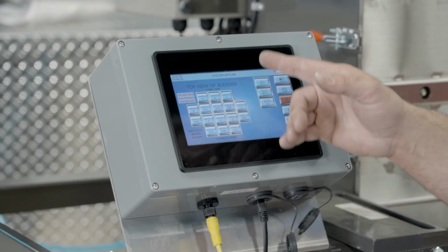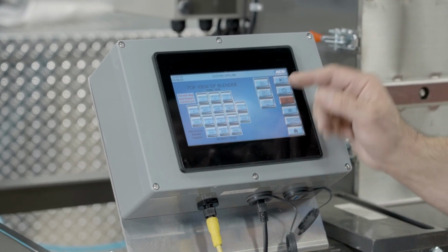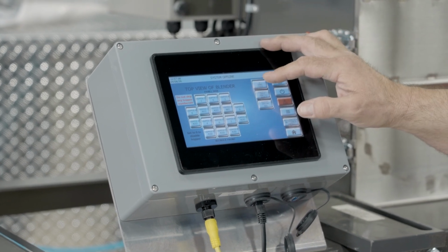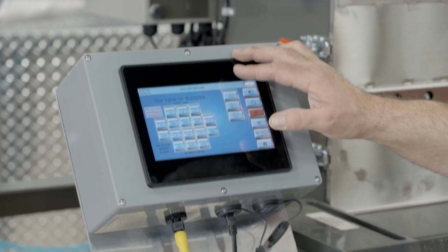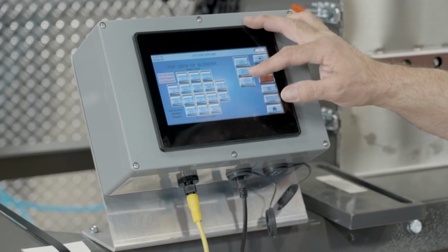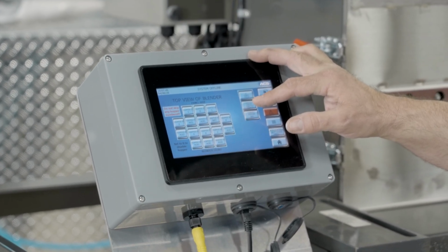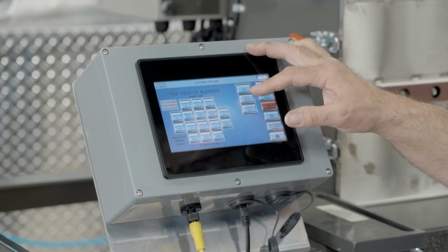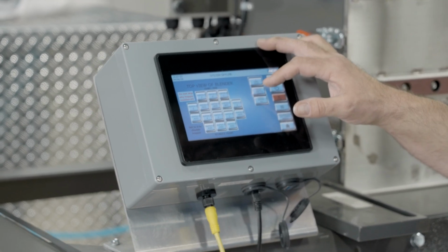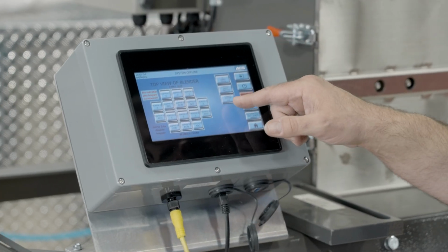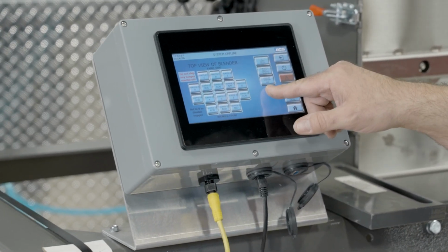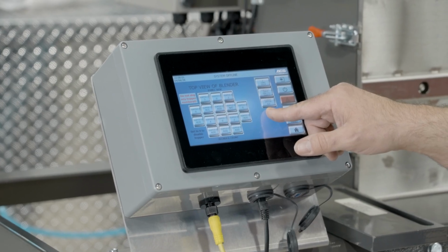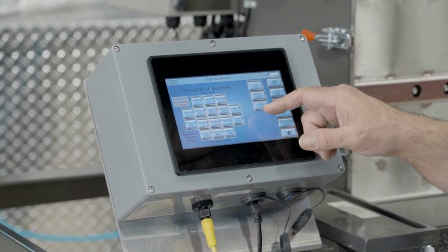Also, if you ever add a component, this is where you'd set it up. You'll see on this side of the screen, it tells you have 2 load cells. Our auger blenders use 1, so this is changeable. It also gives you which load cell input card we're using. So there's more than one selection, so if you ever have an issue with your blender, you have to change it. Just verify you have the right card selected. And we also have a built-in convey system that's an option. So if you purchase that option, you get an extra output card and you can use the built-in convey.